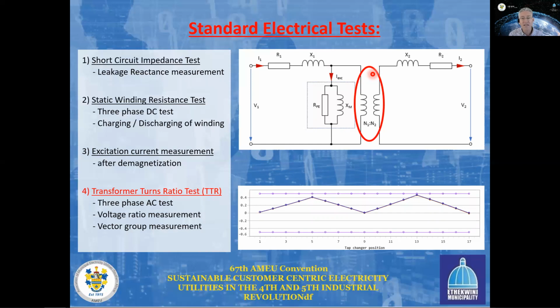And that is an IEC 60076-1 standard that specifies this limit. And you can see here in the test results, it already shows us the plus and minus 0.5% limit. And as long as our measured deviation is within this range, our transformer can be passed and can be switched back as normal.